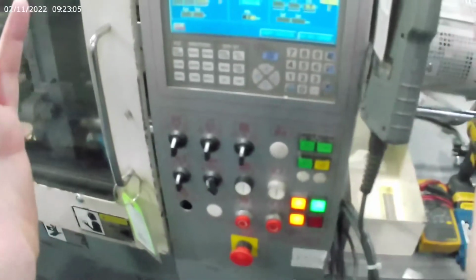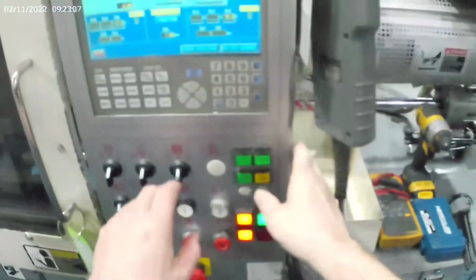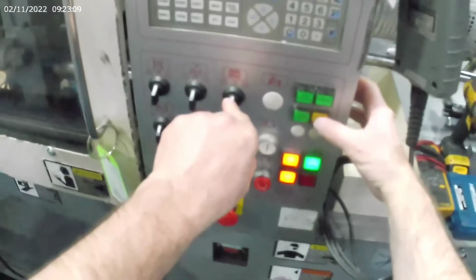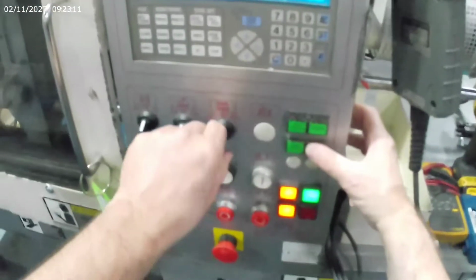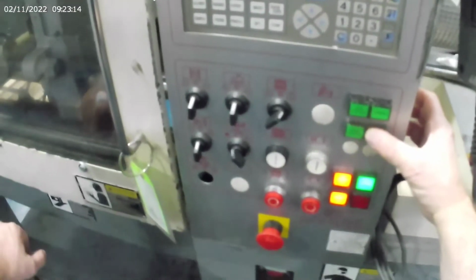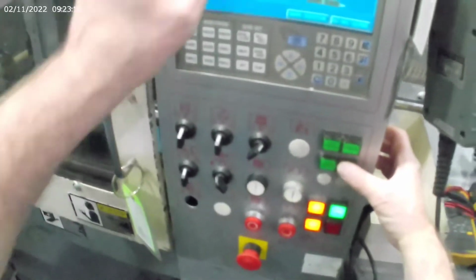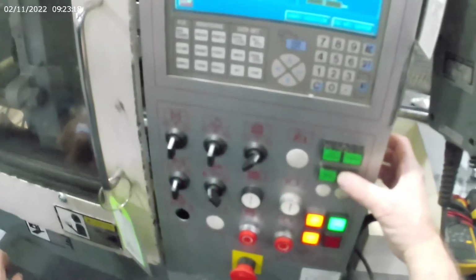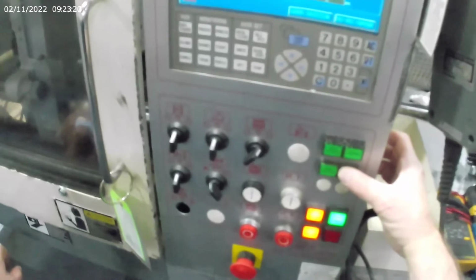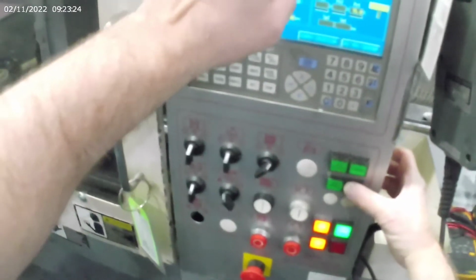Then you do an overall length of the rod. You've got to do the overall length, and the way to do that is hit alarm reset, screw position, suck it back all the way, and it'll tell you when it's reached its overrun. Overrun position reading complete. So the overall span is done on the position, and the 0 point is done.